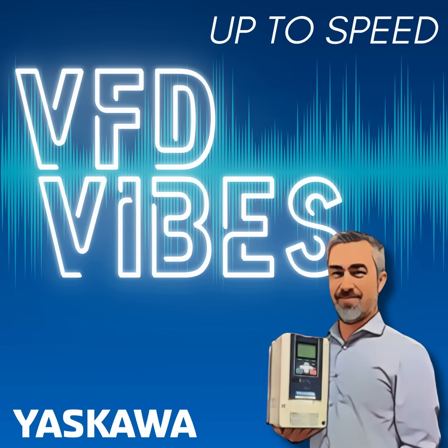Right? Exactly. So aside from, we've been talking a lot about the electrical protection, but are there other instructions when it comes to installation around ventilation or volume or other details of a panel? Another good question, Greg. So when looking at the variety of approved protection devices for drives, which you'd have to look in the instructions, right? It's the only place to find it. You may notice an array of solutions and conditions of use. So a drive manufacturer could say, oh, you can install the drive along with the fuse, or you can install it along with the circuit breaker, et cetera, et cetera. So there's this variety of solutions that a drive manufacturer may or may not provide to you.